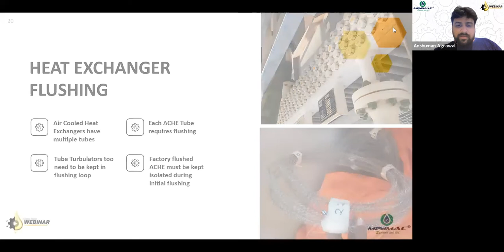The second case study which I would like to discuss here is from another project in Oman, from BP, where a high viscosity lube oil was being used for flushing. And as the system was designed to handle high viscosity lube oil, even the flushing was being performed with high viscosity oil. So the challenge was that even at 2x or 3x of the lube oil pump flow rate, flushing was not being achieved in an efficient manner.